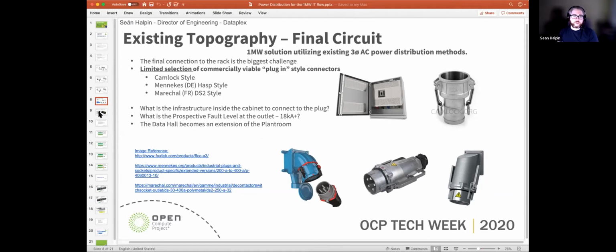Typically your standard MCB or whatever, up to a point, is anywhere between 10,000 to 16,000 amps. You don't want it to go really above 10,000 amps at the rack. So that is a challenge in of itself now with the increased load.